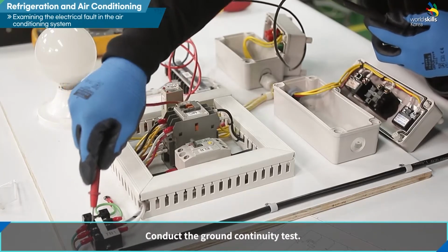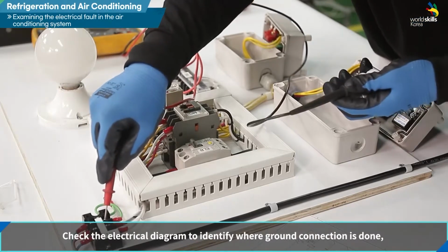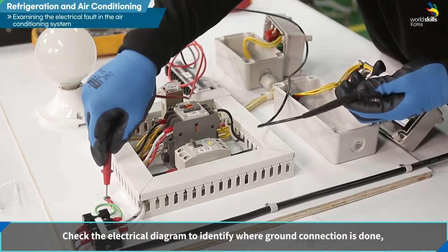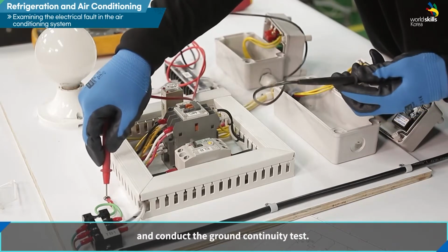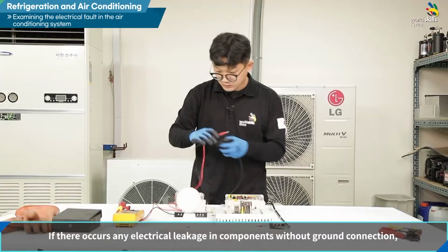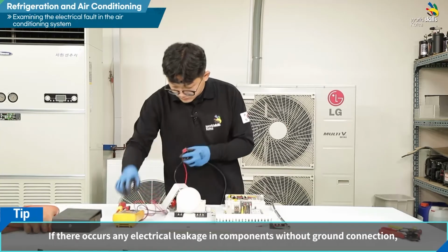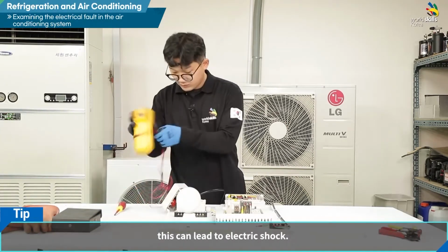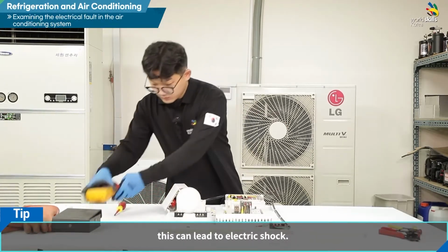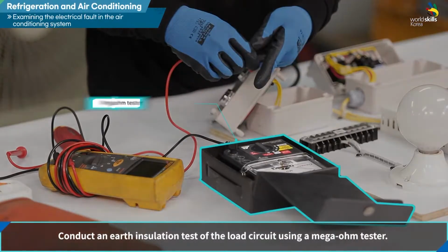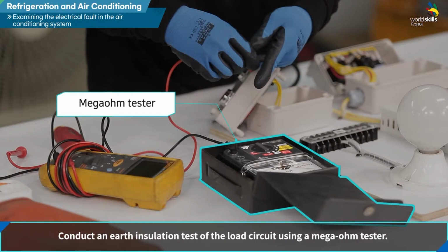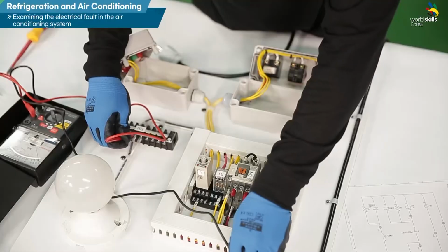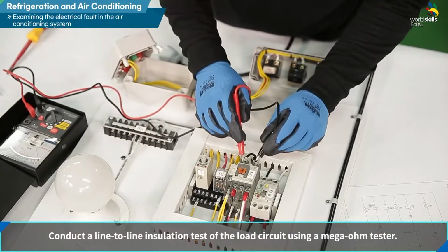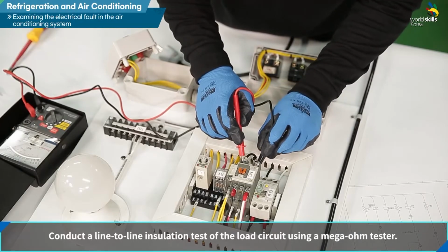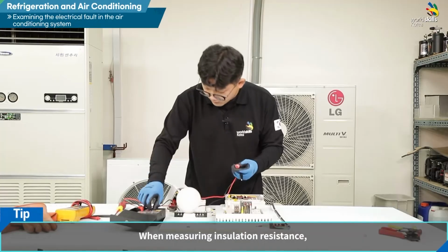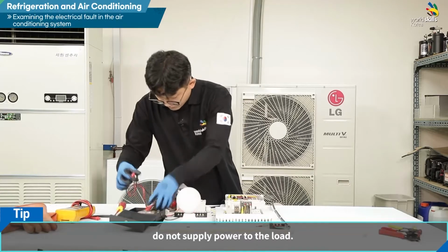Conduct the ground continuity test. Check the electrical diagram to identify where ground connection is done, and conduct the ground continuity test. If there occurs any electrical leakage in components without ground connection, this can lead to electric shock. Conduct an earth insulation test of the load circuit using a mega-ohm tester. Conduct a line-to-line insulation test of the load circuit using a mega-ohm tester. When measuring insulation resistance, do not supply power to the load.